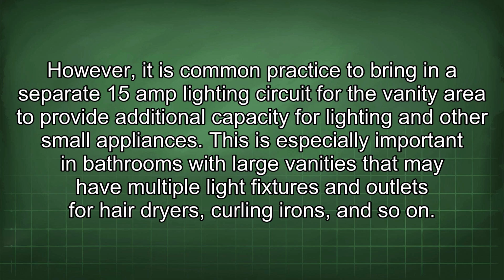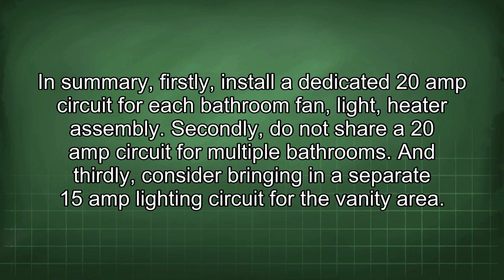irons, and so on. In summary, firstly, install a dedicated 20-amp circuit for each bathroom fan, light, heater assembly. Secondly, do not share a 20-amp circuit for multiple bathrooms. And thirdly, consider bringing in a separate 15-amp lighting circuit for the vanity area.